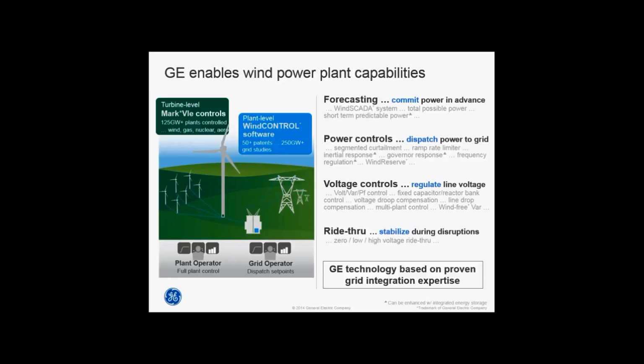In terms of voltage or frequency controls, we have the same capabilities. We can look at droop compensation, line drop compensation, plant communications, and VARs as they're needed. We have power factor settings we can apply so things respond in real time to manage a smooth curve.